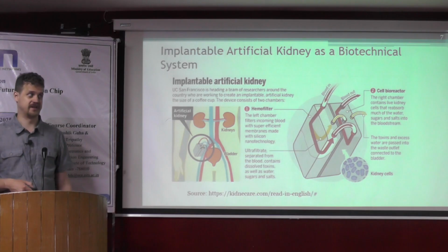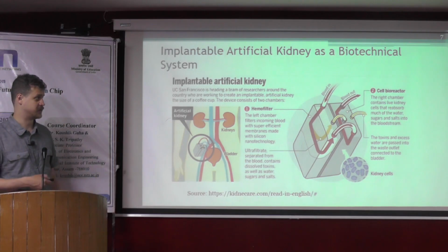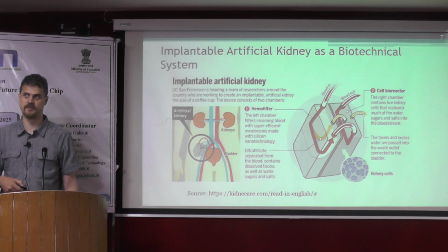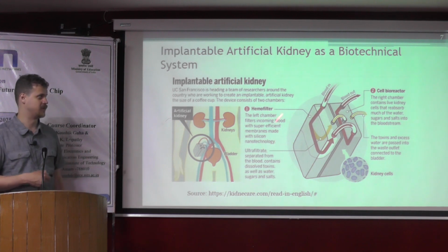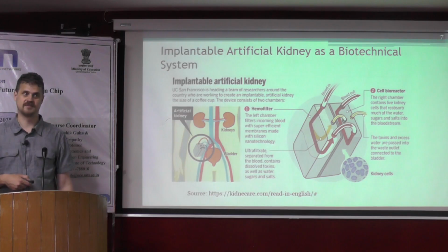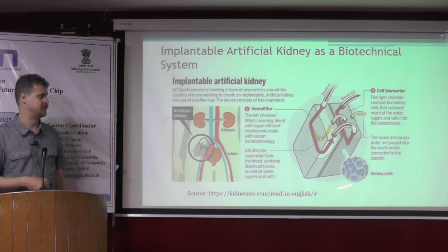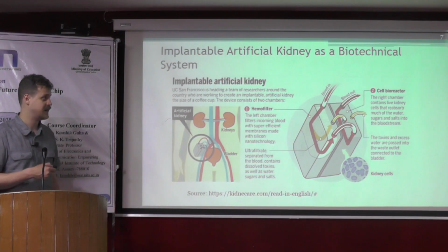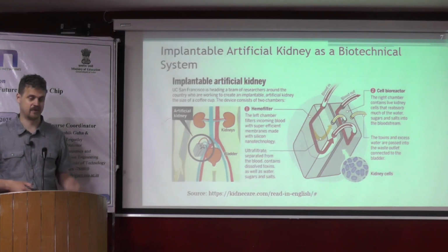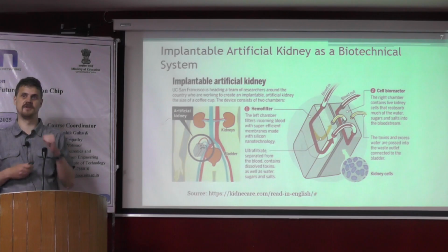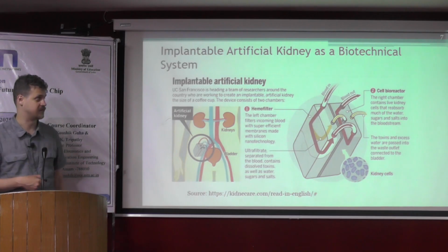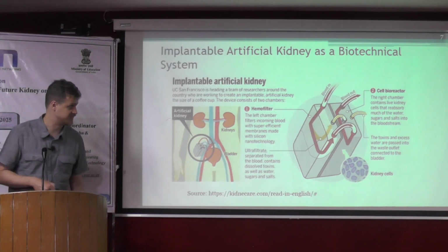Just like I said, we need to maintain control over the microfluidic system to make sure that it operates properly, that we achieve a proper blood filtration rate, so we can remove enough excess water from the human organism, and that we provide proper clearance of specific uremic toxins like urea and creatinine. Overall, we need to make sure that there is no leakage of blood within the microfluidic system.